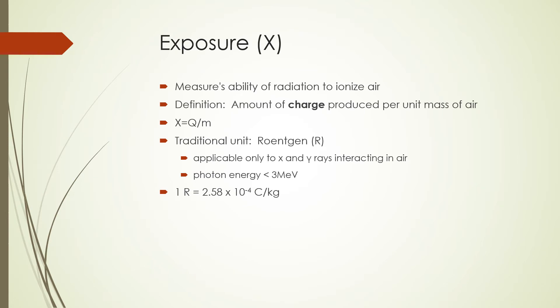Since the discovery of x-rays and gamma rays, their measurement has presented technical difficulties. In the early years, Röntgen used the blackening of photographic film emulsion as a measure, but the response of photographic film is nonlinear as well as energy dependent. For many years, skin reddening dose was used as a measure for evaluating radiation treatment effects, though there was a problem with biological variability and lack of objective measure of reddening. In 1928, the Röntgen R was defined as the principal unit of radiation quantity for x-rays of medium energy, refined over the years until it was recognized that ionization can be directly measured with air-filled radiation detectors. One Röntgen is equal to 2.58 times 10 to the power negative 4 coulombs per kilogram.